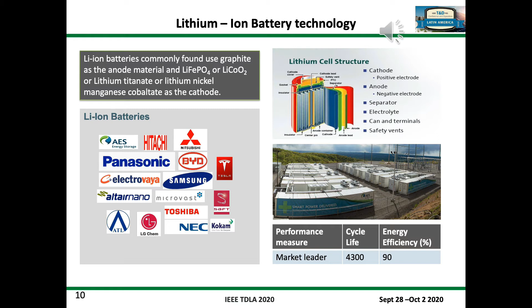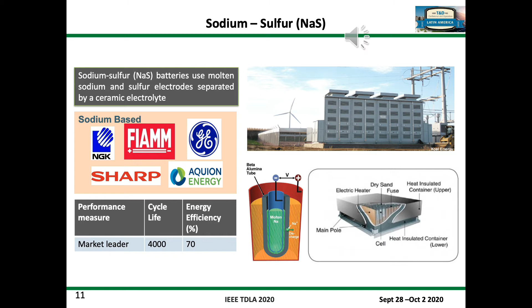Sodium sulfur is probably the second most common battery technology. A challenge with these installations is the operating temperature, which is in the order of 270 to 350 degrees Celsius, and the need to use electric heaters to keep the temperature at those levels. There are quite a few fewer companies active in the market when compared to lithium-ion batteries. Typical life cycle is 4,000 cycles, and energy efficiency is in the order of 70%. The picture shows a real-world installation of this type of batteries in the US, along with a wind plant that you can see in the picture.